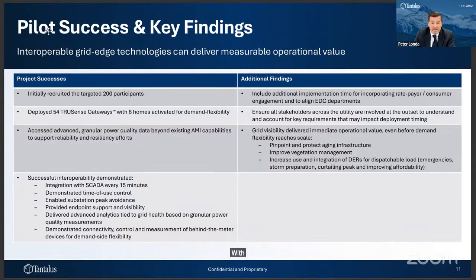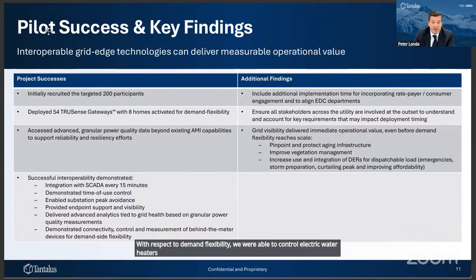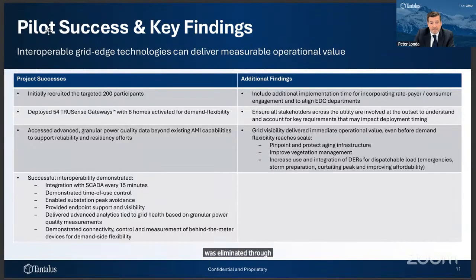With respect to demand flexibility, we were able to control electric water heaters and confirmed that almost 100% of the baseline electric consumption was eliminated through triggered events. On average, the flex capacity water heater translates into approximately 5.5 kilowatt hours of controllable demand.